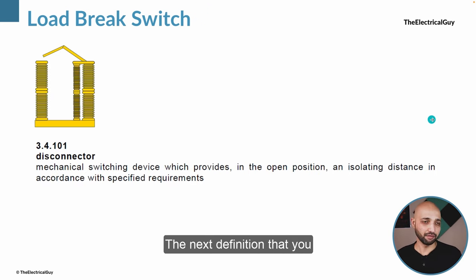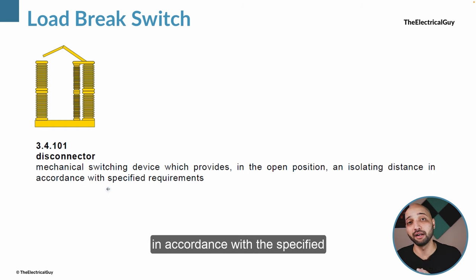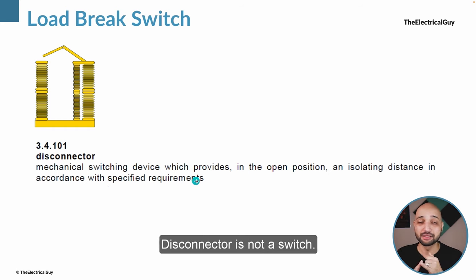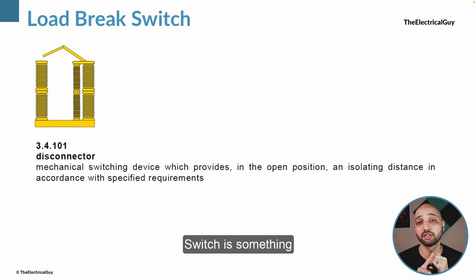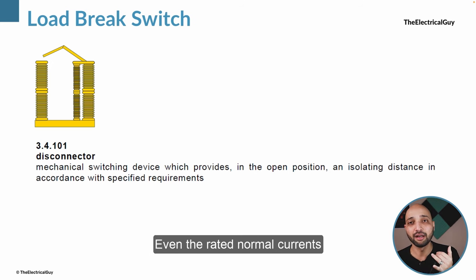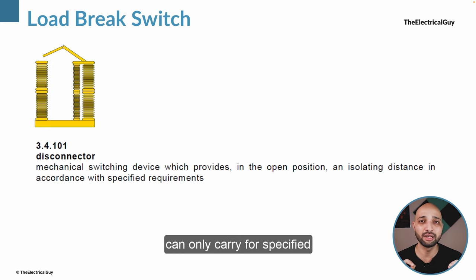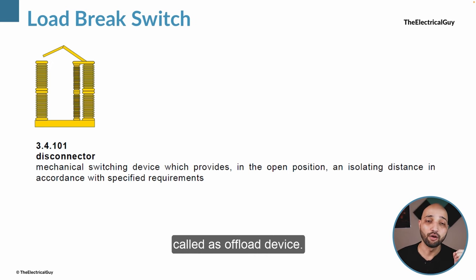The next definition you should understand is a disconnector. IEC says a disconnector is a mechanical switching device which provides, in the open position, an isolating distance in accordance with specified requirements. Importantly, a disconnector is not a switch. A switch can carry, make, and break current. Disconnectors are not capable of doing any of those things — even rated normal currents they cannot make or break. They can carry current but cannot make and break it. Even for short circuit currents they can only carry for specified time limits. That is why it is called an off-load device.